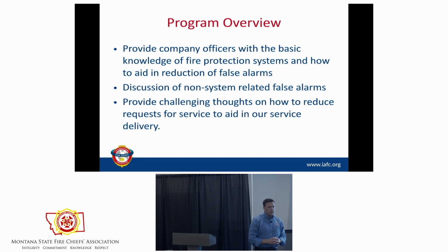In the one case, it was a faulty duct smoke detector up in a rooftop, and it was really the wire connection, right? A very vulnerable source. Outdoor rain, moisture, cold, not a great spot for a duct smoke detection. In the other case, it was a church, okay? And every time the power went out, the fire alarm went off. And I'm not just saying the fire alarm panel.